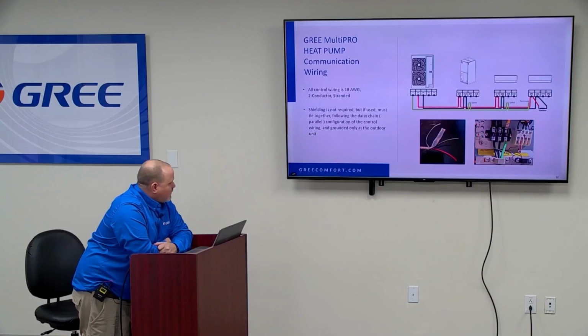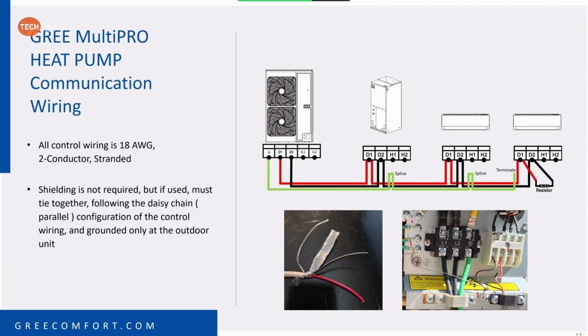All right, moving on. I want to talk about the wiring a little bit. It is not required that you use grounded shielded wire with MultiPRO, but it is highly recommended, just to shield out any interference. If you're going to do grounded shielded, it's very important that you do it properly. Our recommendation is that you hook that grounded shield wire, this bare wire right here, to the outdoor unit.